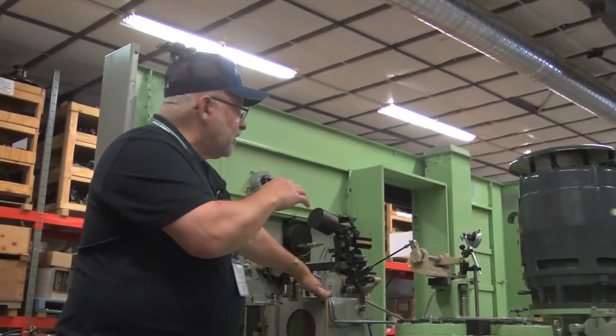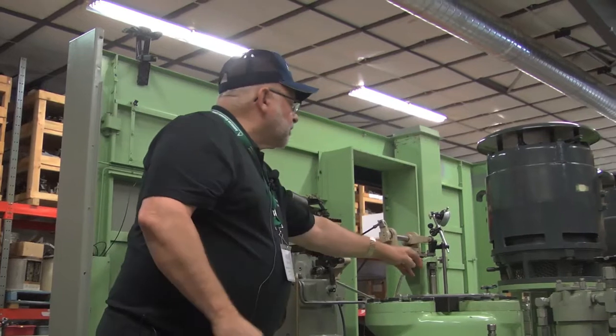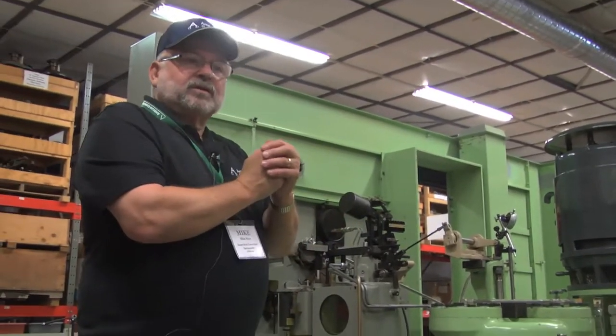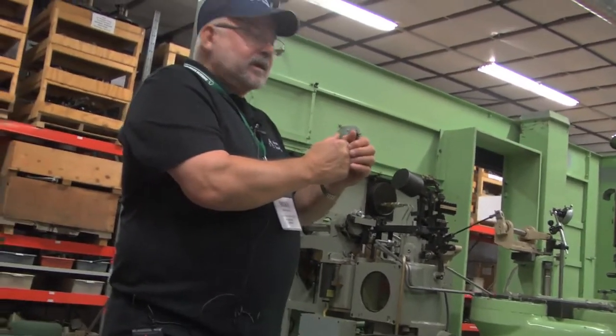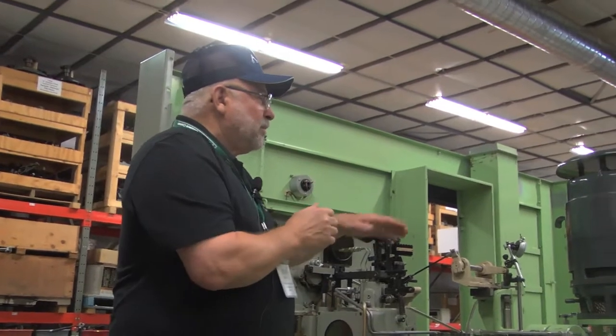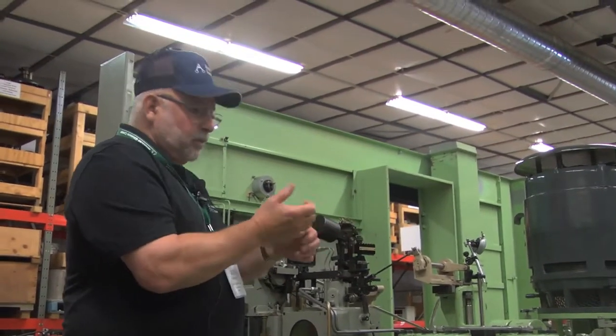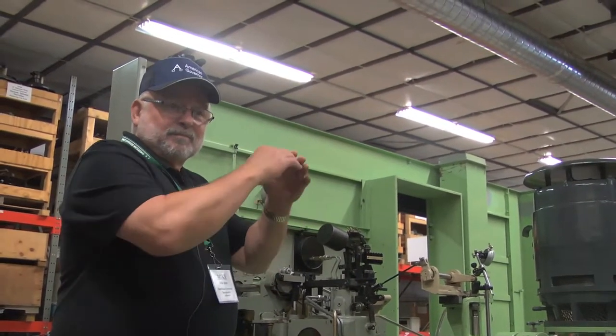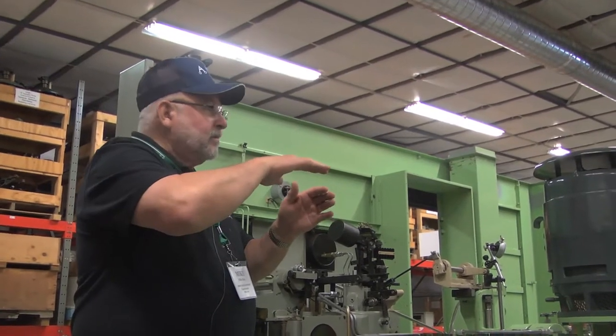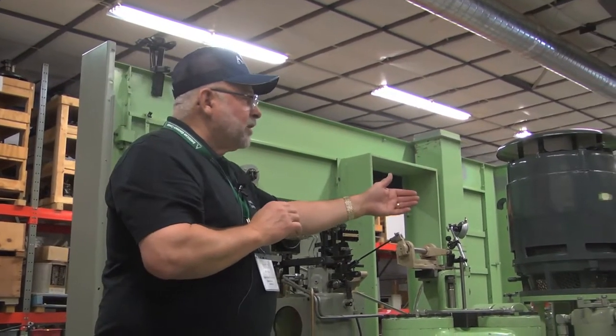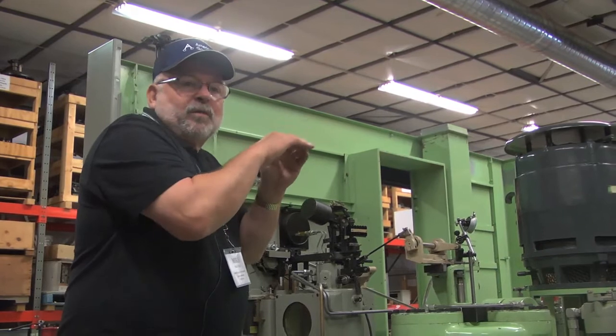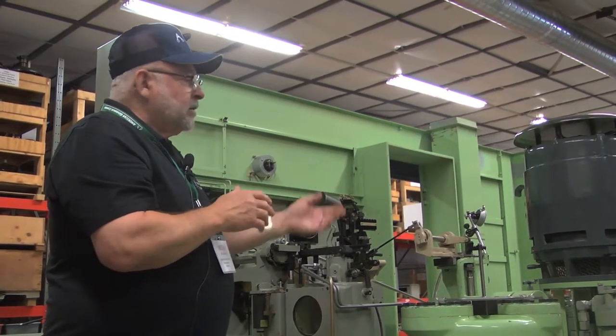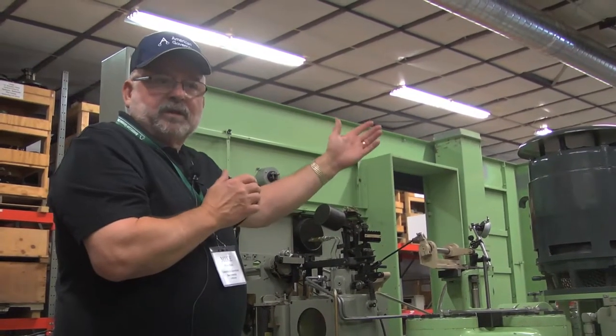Well, a lot of times you'll see it limited on the open because some of them have a PRV on them, and the movement would pop the PRV open on some of the models like Newport News, Allis Chalmers. It would pop them open, then they'd have to dispatch an operator to close it again, so they slowed down the opening, which it'll still load the megawatts per minute.